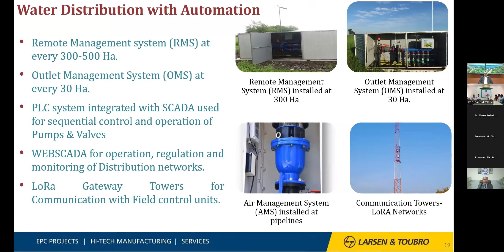Then, to make the communication, we are using LoRa gateway towers, which work on radio frequency. The system works through that, and all the data goes to the web SCADA for further operation. And then there are certain other features. As I told, we have kept a 132 by 11 kV switchyard at the site itself to have dedicated power for our system. Power is the critical resource. So we have this 132 by 11 kV switchyard at site, which has a dedicated line from a 220 kV switchyard. And to maintain the power factor, we have installed a capacitor bank to keep the power factor above 0.95. That is also where we are getting the incentive.